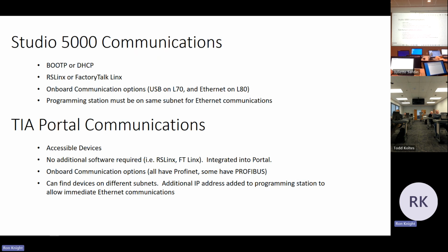So there is a chance that you could run, and this is a bad example, but there are HSPs, or hardware support packages, that you can download from the Siemens website. It's like downloading an EDS file from Rockwell to make the software know what it is. But if the hardware is so new that version 16 doesn't know it, then at that point, what you really need to do is flash the firmware down to 2.8 or whatever it is that version 16 would know about.